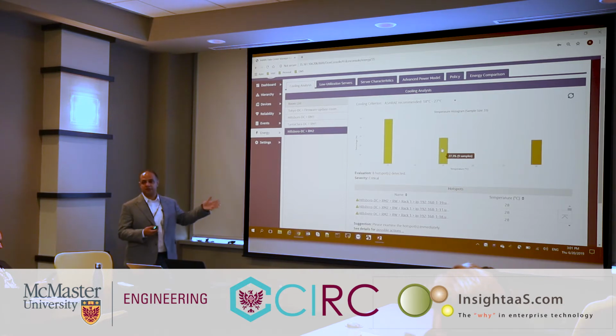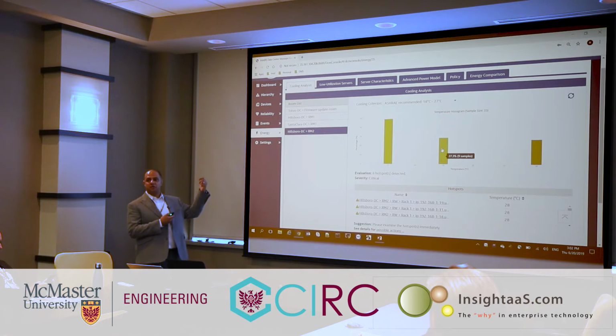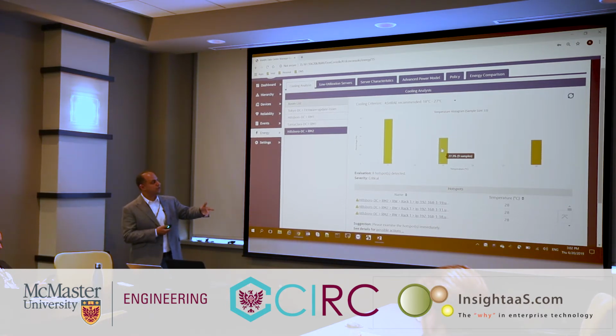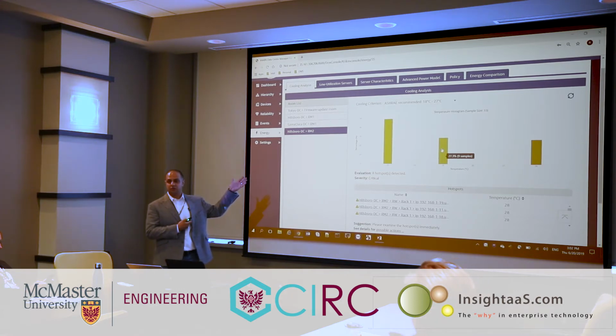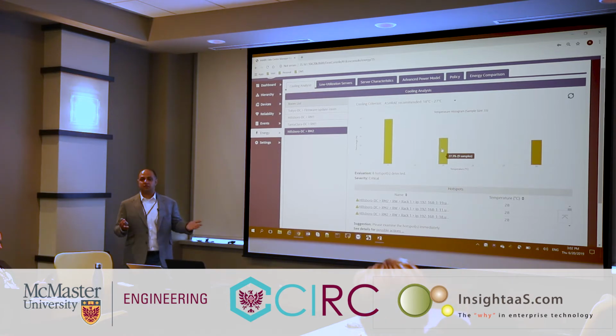the temperatures of all the systems in that room. And while it was reported as the highest temperature room, we're actually seeing that most of the servers are running cold. Only a few of them are running hot. So with one graph, you can make deductions like, okay, maybe these guys have component health issues. So I'd correlate that with the information that I see about the system health and see if that's the case. Or I can correlate that with the layout that I just showed you and see if it's an airflow problem.